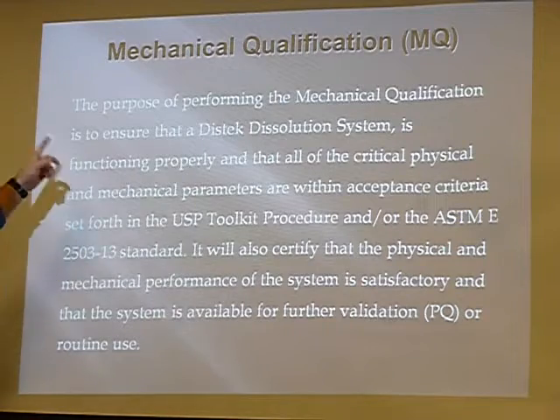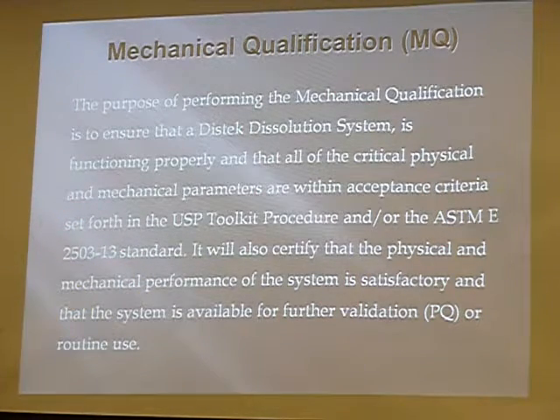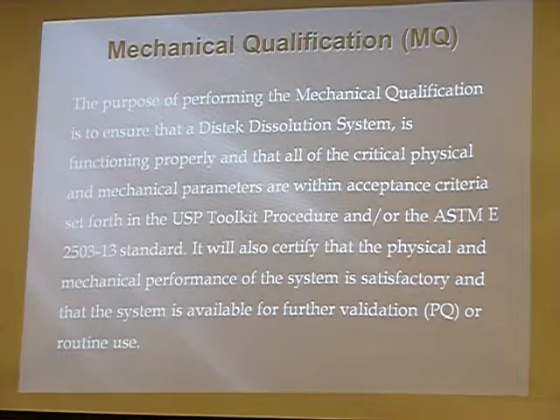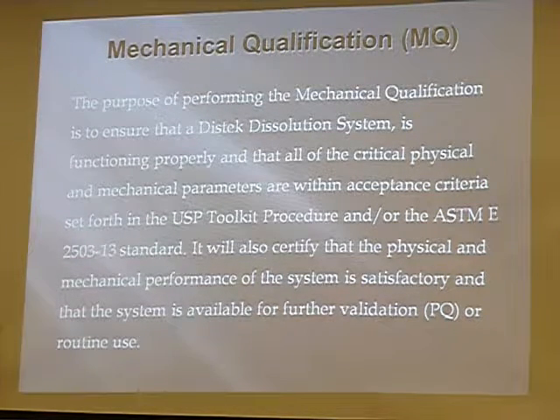This also will certify the MQ, that the physical and mechanical performance of the system is satisfactory and that the system is available for further validation, the PQ, or routine use. If it's a mechanical qualification, they can go strictly right into using it when we're done with the MQ after they go through their SOPs and they prove it. Or it's now ready to do the performance verification test. But we're testing all the mechanical capabilities of the unit, hence the mechanical qualification. This is the pass-fail. This is all the specifications that are going to get measured with our devices that we use, our hand tools, and this is how the document's laid out.